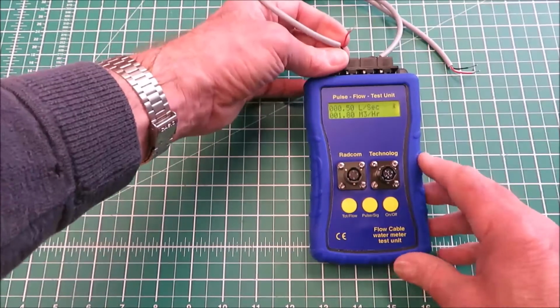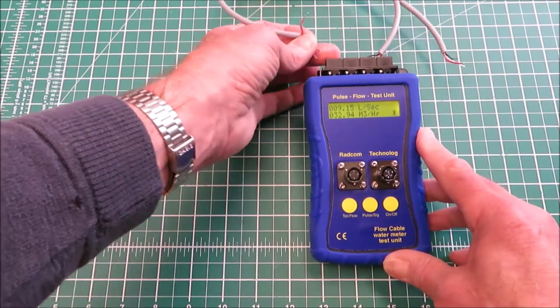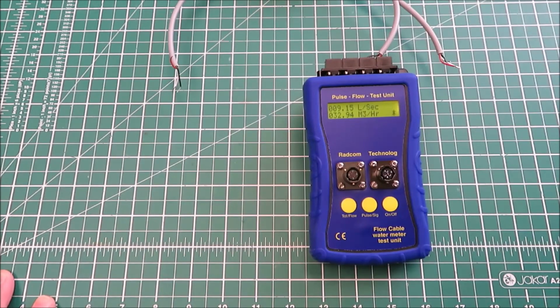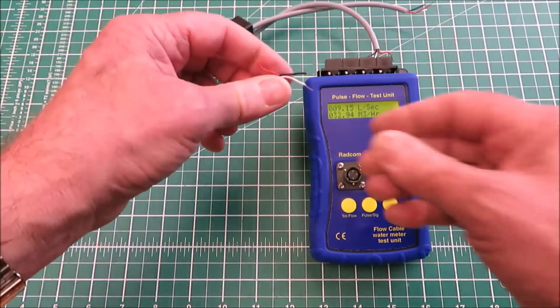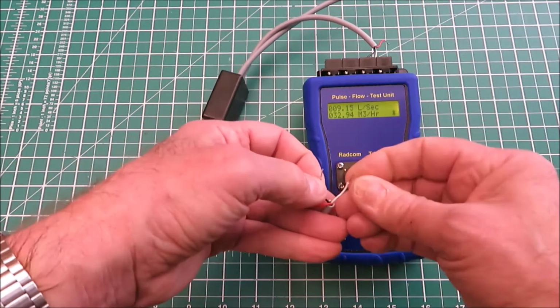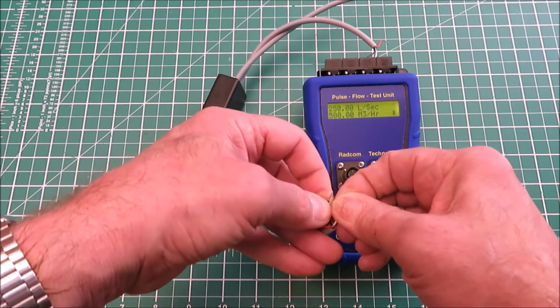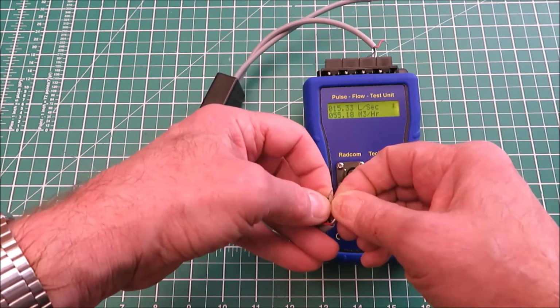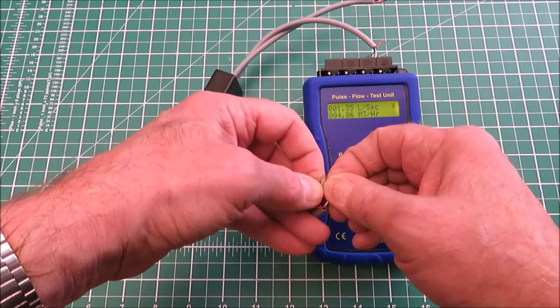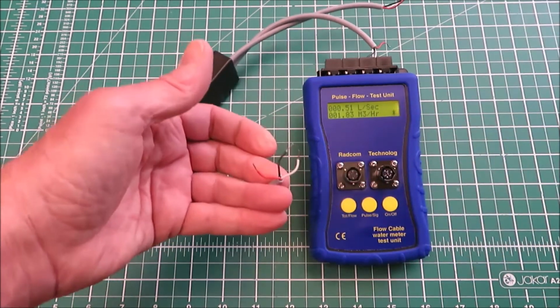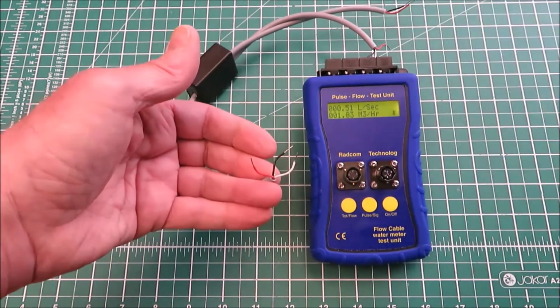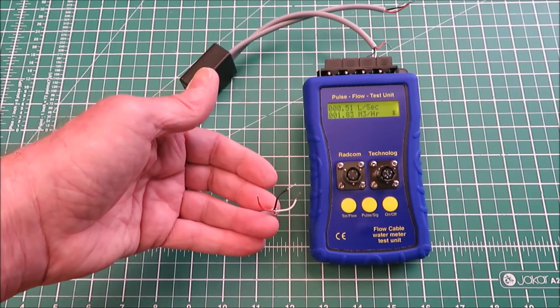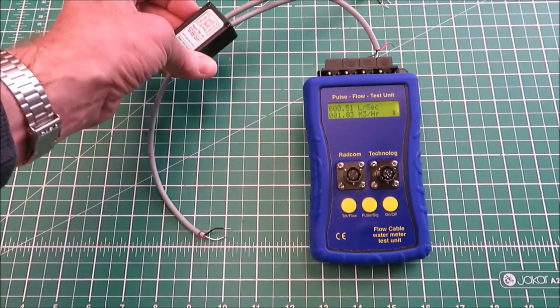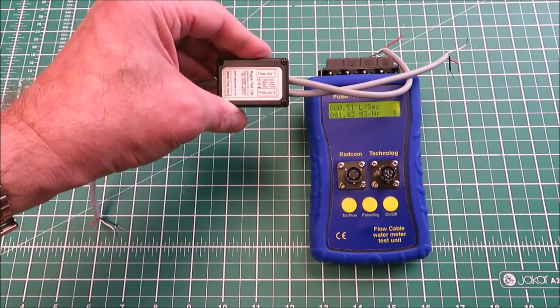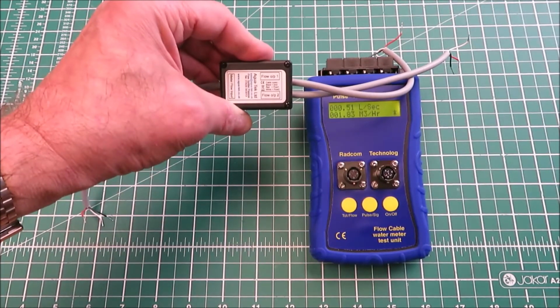If I disconnect the input to the splitter, you can see that it's now ceased to indicate a flow. But actually, if I get hold of the black and white wires and take my hands out of the way of the screen and do that, that's it, mimicking a flow. Of course, if you had a flow meter and the flow sensor was connected, you could just put the output of the pulse splitter into the pulse test unit. And that's how to test a passive flow splitter.